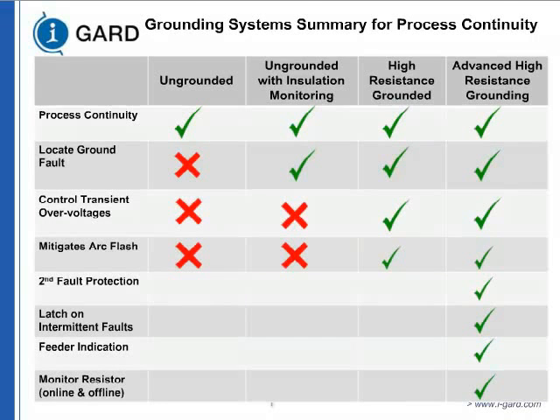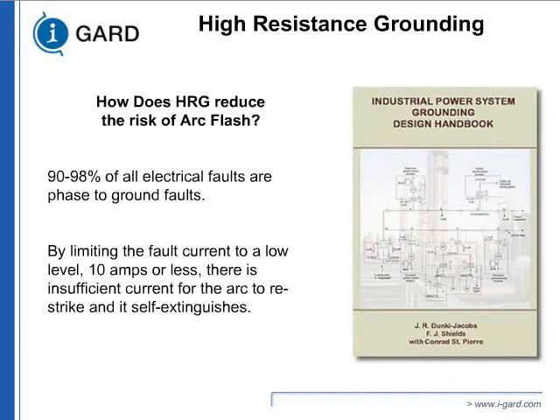I mentioned that it mitigates arc flash. It reduces the risk. It doesn't reduce the incident energy if the phase-to-phase fault happens. How can we say that? Industry data indicates that 90 to 98% of all electrical faults start as phase-to-ground faults. If they are not cleared, then they go into a phase-to-phase fault condition. If you can limit the ground fault to a low level, say 10 amperes or less, the probability is very low that it will go to phase-to-phase. If you have a solidly grounded system, the first fault will be a 20,000 amp or 10,000 amp fault. That fault will quickly go to phase-to-phase if it's not cleared. So that's where we can say it reduces the arc flash risk.